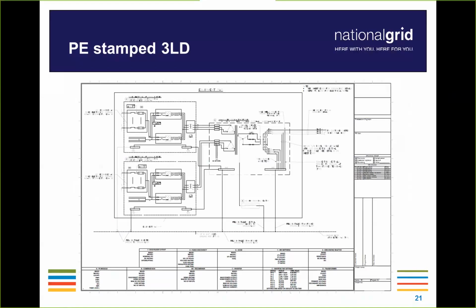And so the first question I would ask, if this was new to you, would be, why do I need to have a single line diagram versus a 3-line diagram? In most cases, if it is a 3-phase service, the 3-line diagram will be required. The reason is that once we get into three-phase diagrams, if you represented, for instance, a delta Y transformer, which I pick on because this image has a delta Y transformer, in the three-phase representation it's more readily apparent that that is exactly what that transformer is, because you have to actually physically draw it that way on your three-line diagram.